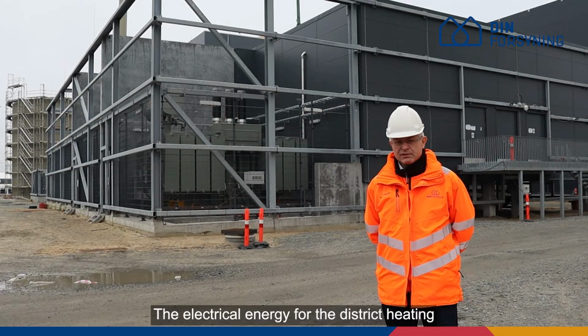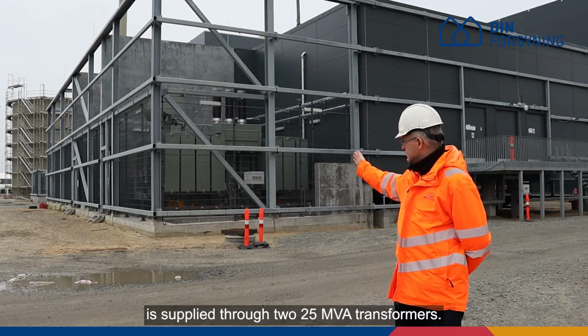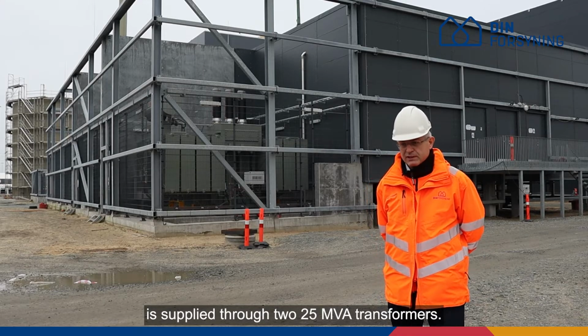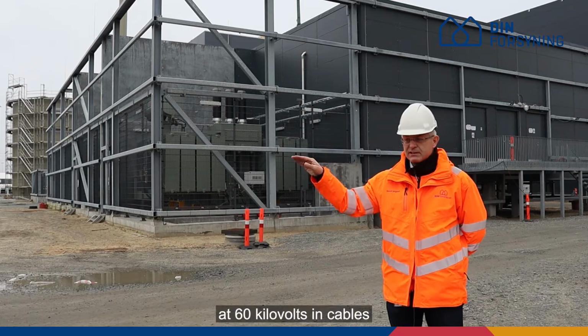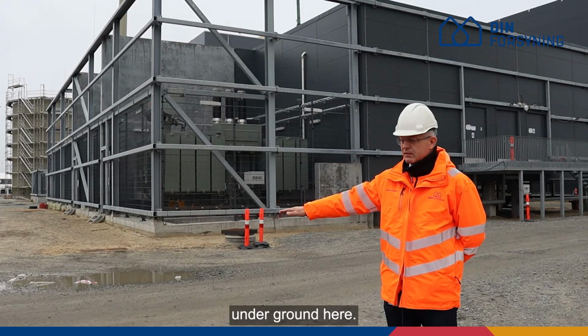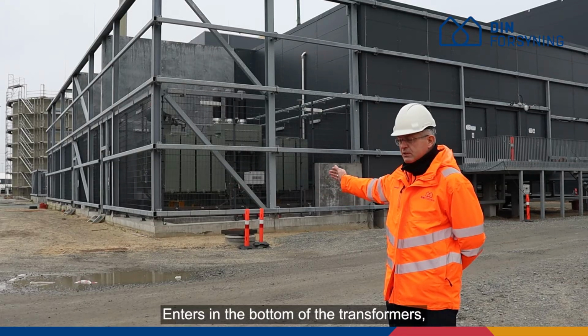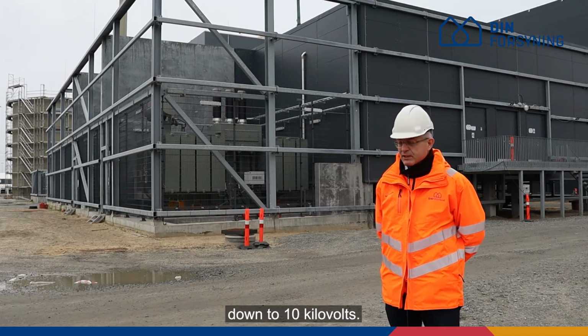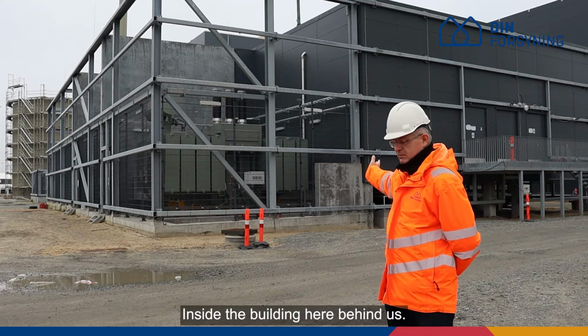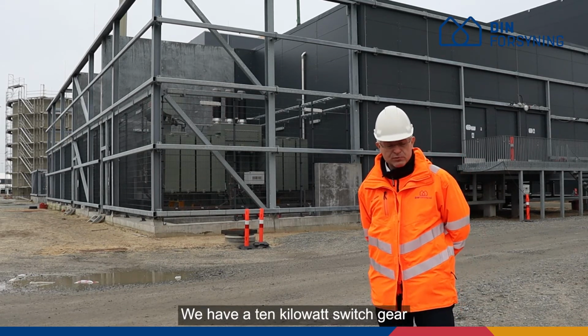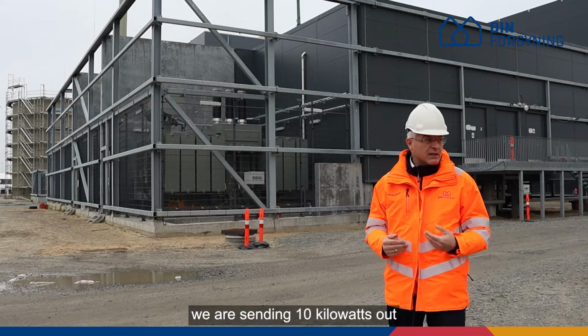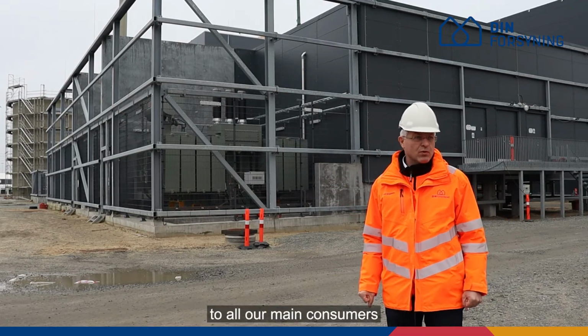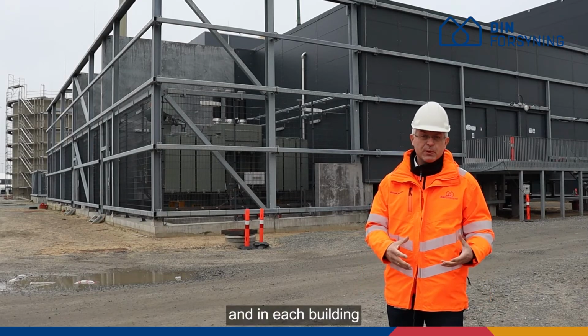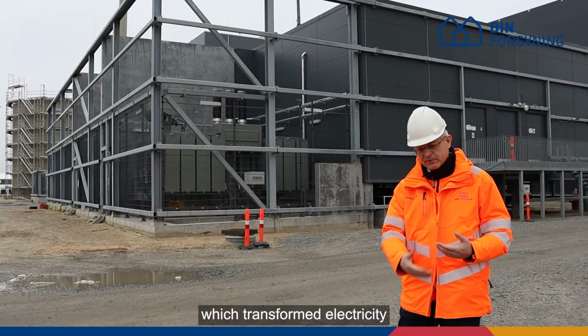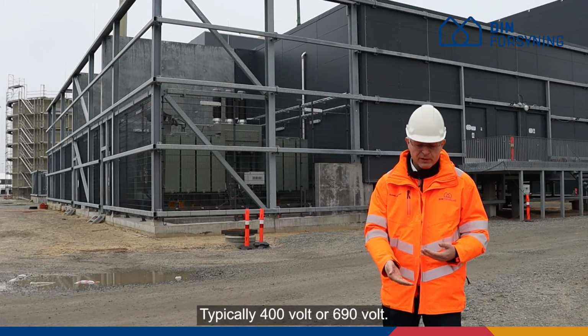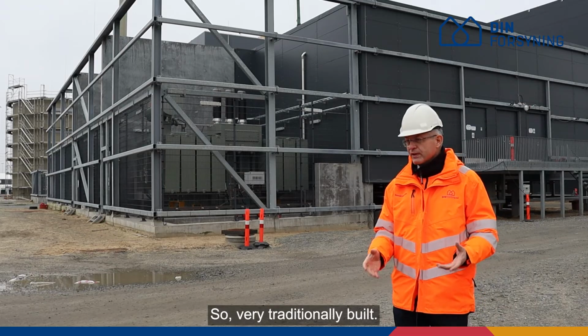The electrical energy for the district heating for the future plant is supplied through two 25 MVA transformers. The electrical energy arrives at 60 kilovolts in cables underground here, enters in the bottom of the transformers, which transform the electricity down to 10 kilovolts. Inside the building here behind us, we have a 10 kilovolt switch gear. And from the switch gear, we are sending 10 kilovolts out to all of our main consumers, and in each building we have a transformer there which transforms the electricity down to the different consumers, typically 400 volt or 690 volt. So very traditionally built.